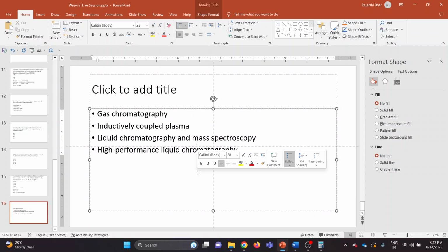Further, those droplets are converted into an aerosol form. Those aerosols then reach a plasma region, a superheated region, where the atoms of different metals, heavy metals, absorb the energy. Once they absorb the energy, they become super excited. Then they quickly come back to their stable state by releasing energy. And that wavelength of energy released from those atoms is like a signature emission for different kinds of metals present there.